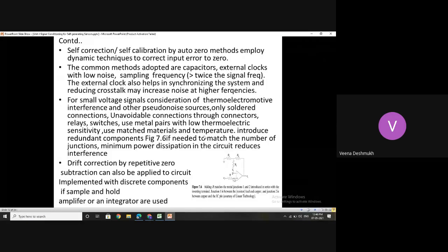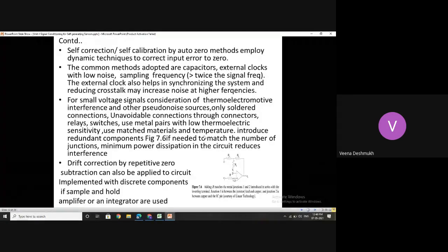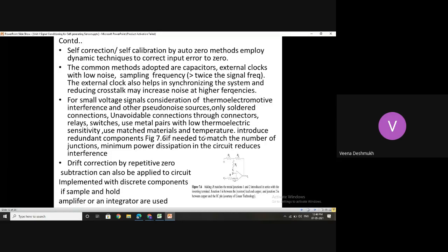One switch to ground is always connected: for the measurement sensor there is a switch provided, so at one time it switches to the actual sensor signal and at another time it switches to ground. Whenever ground is connected, the potential is measured and continuously added to the signal being measured. By doing this, we can minimize the drifts, and any temperature variations happening can be taken care of.